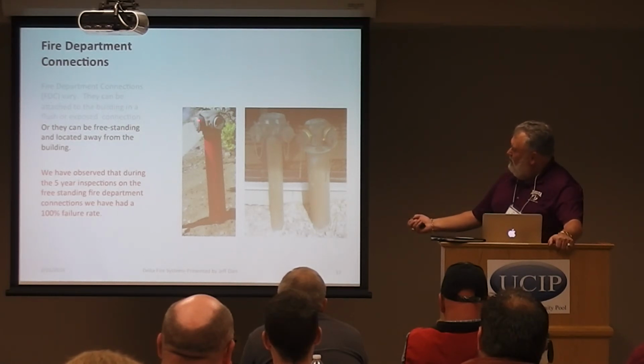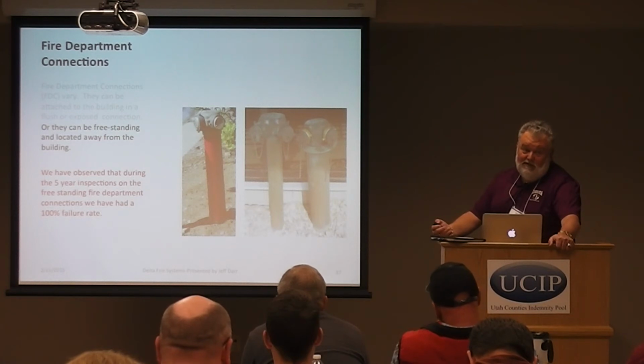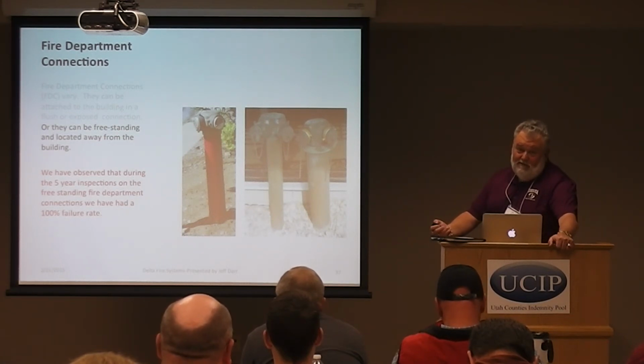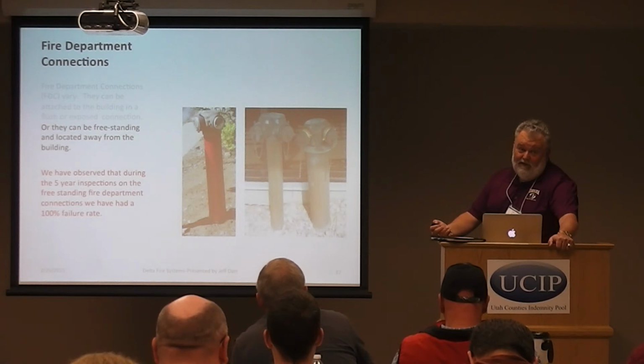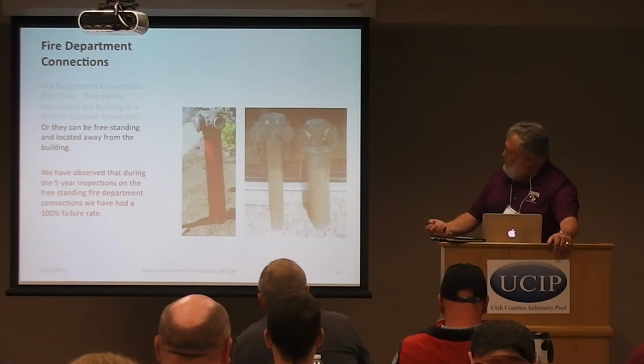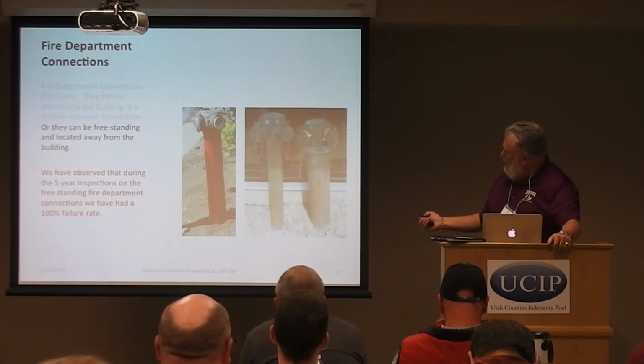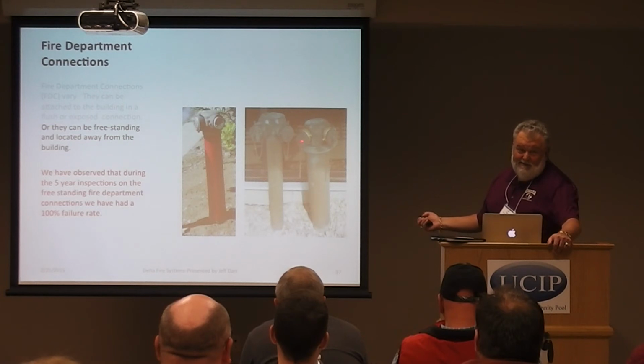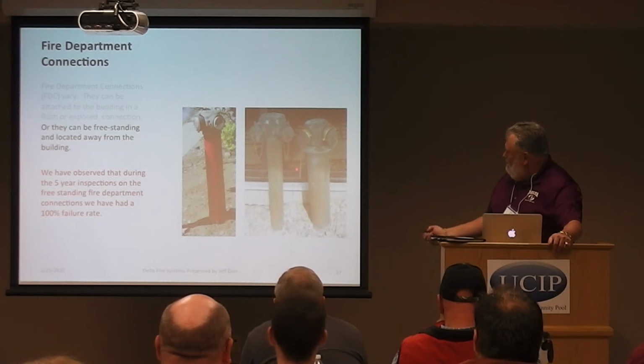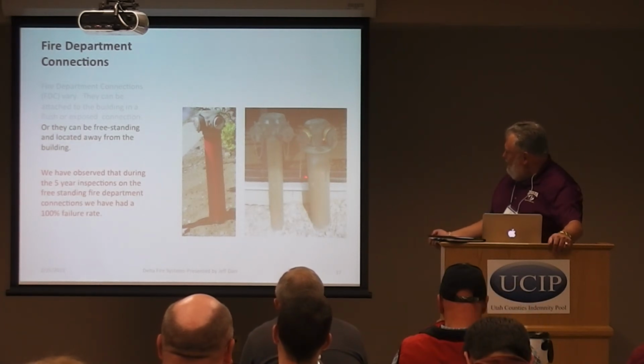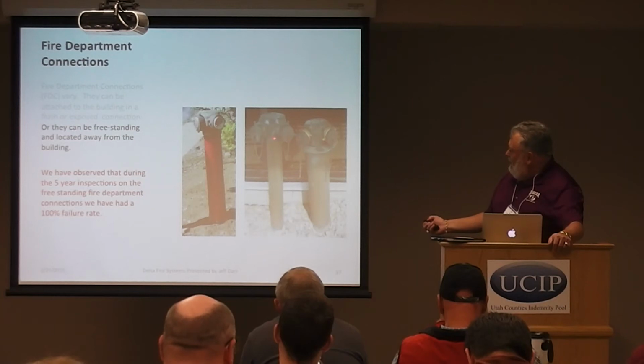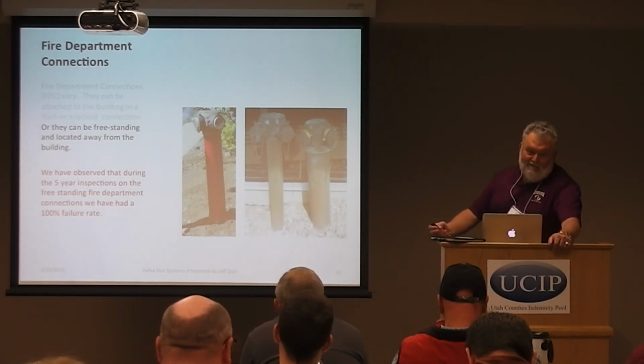Now, you can see these have what we call Knox caps. The only way to get those off is the fire department has a key that will fit, that they can take them off. That's a deterrent to keep people from stealing them. You can see this one, the new brass versus the old brass. Someone's taken part of that off there. The other reason, and the chains for these caps are hanging loose, they were probably attached like these. They couldn't get the cap off to start with, so they just took the outer part and they had to do that to replace that.